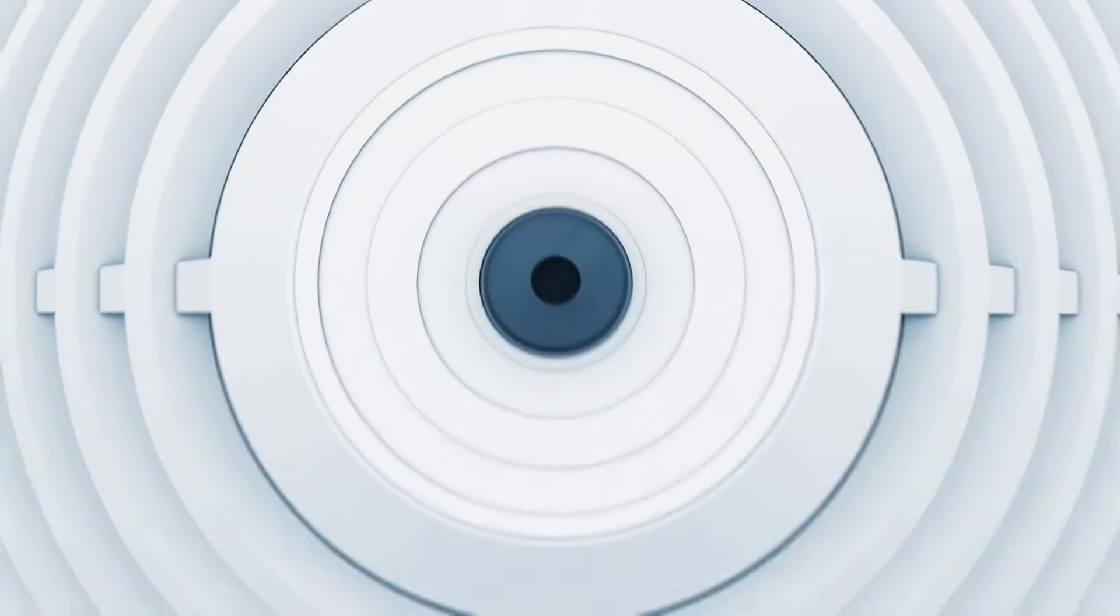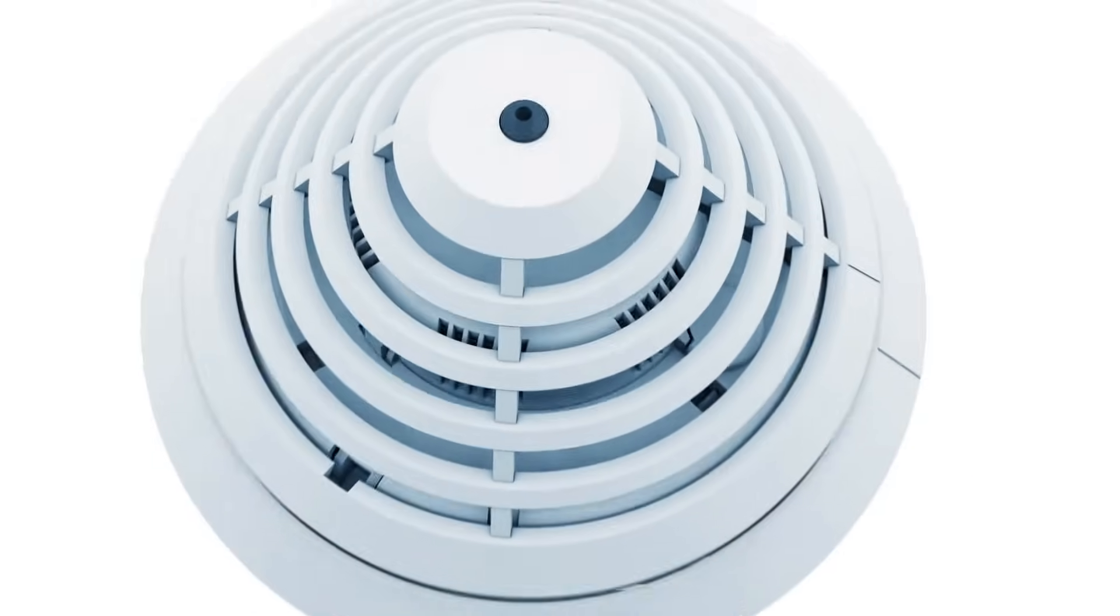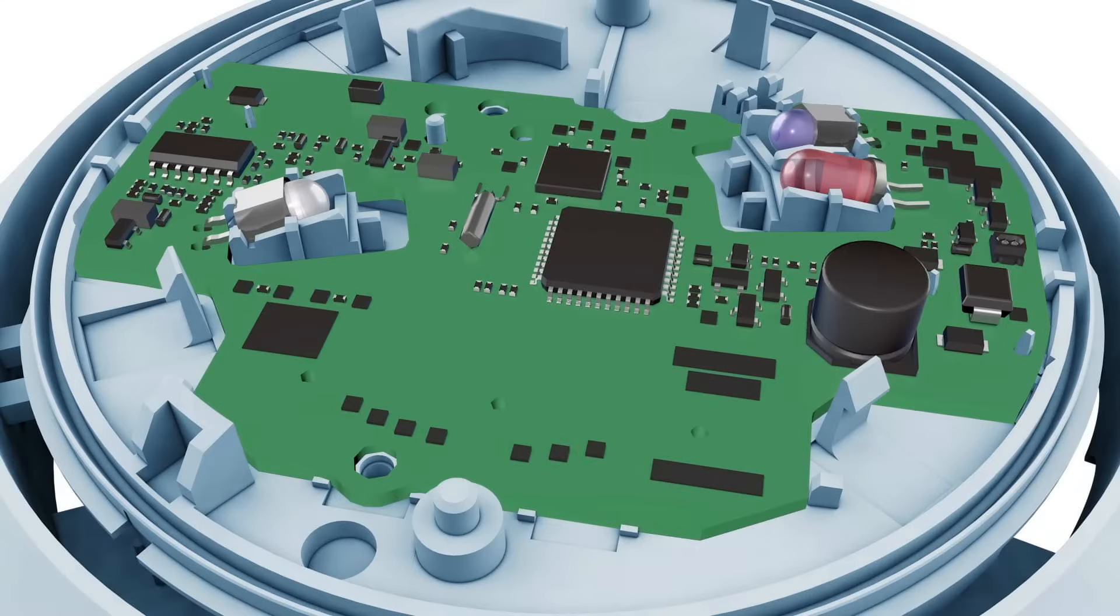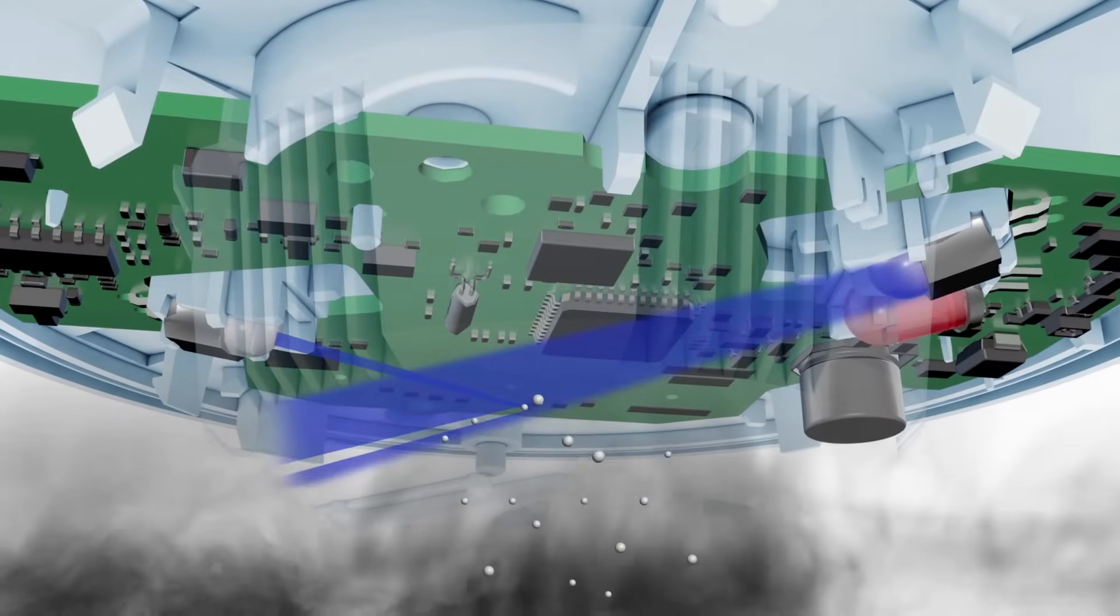Detector types with dual-ray technology are particularly effective at identifying the tiniest traces of smoke early. They have two optical sensors, one with an infrared and one with a blue LED. Thanks to their different wavelengths, the detectors are able to measure the exact density and size of the smoke particles.